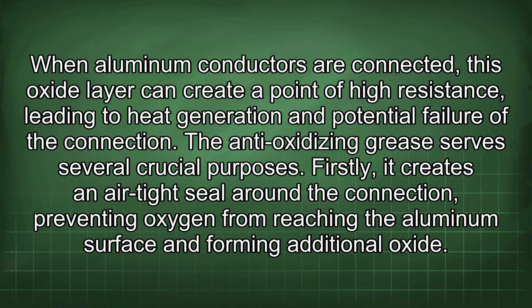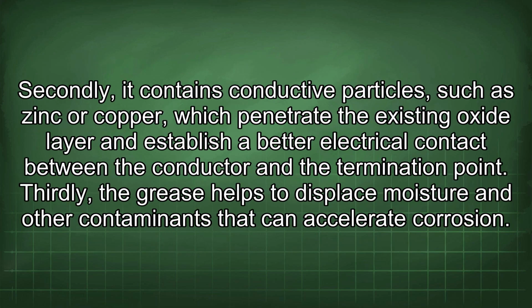When aluminum conductors are connected, this oxide layer can create a point of high resistance, leading to heat generation and potential failure of the connection. The anti-oxidizing grease serves several crucial purposes. Firstly, it creates an airtight seal around the connection, preventing oxygen from reaching the aluminum surface and forming additional oxide. Secondly, it contains conductive particles such as zinc or copper, which penetrate the existing oxide layer and establish a better electrical contact between the conductor and the termination point. Thirdly, the grease helps to displace moisture and other contaminants that can accelerate corrosion.